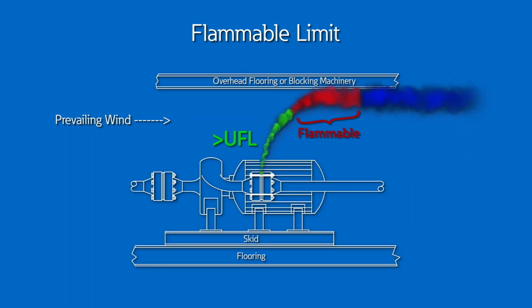The upper level is known as the upper flammable limit, and any concentration above this limit is too rich to ignite. On the lower end, the minimum amount of vapor or gas that must be in the atmosphere is the lower flammable limit. Any fuel in the atmosphere below this limit will be too lean to burn or explode.